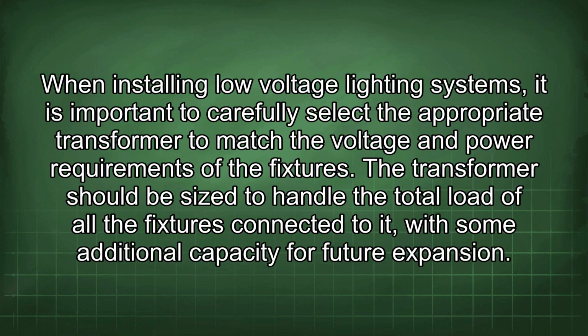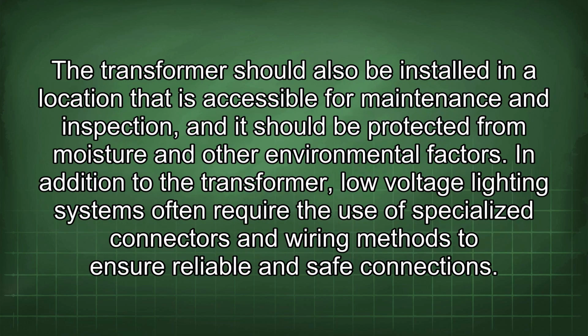performance. When installing low-voltage lighting systems, it is important to carefully select the appropriate transformer to match the voltage and power requirements of the fixtures. The transformer should be sized to handle the total load of all the fixtures connected to it, with some additional capacity for future expansion. The transformer should also be installed in a location that is accessible for maintenance and inspection, and it should be protected from moisture and other environmental factors.